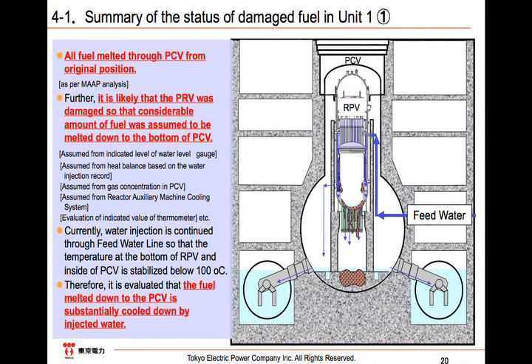From the above, we will summarize the status of each unit. It is assumed that a considerable amount of the damaged fuel in Unit 1 has melted down to the bottom of the PCV. This assumption is consistent with the MAAP analysis, the indicated level of the water level gauge, and mainly the heat balance evaluation based on the water injection record. Also, we think it matches the fact that the cesium concentration in the PCV is higher than that of Unit 2, and that the exposure dose is high at the RCW lines. Currently, water injection is continued through the feed water line so that the temperature at the bottom of the RPV and inside of the PCV has been stabilized below 100 degrees.